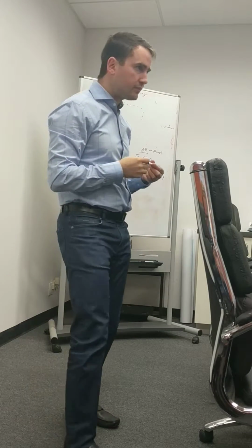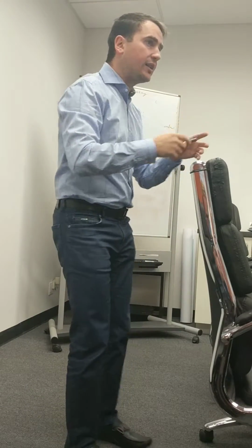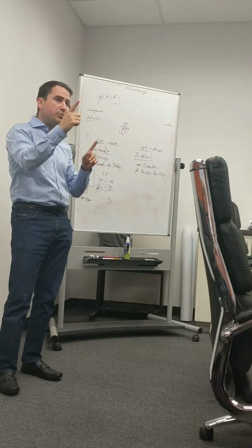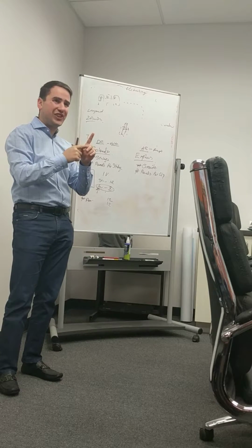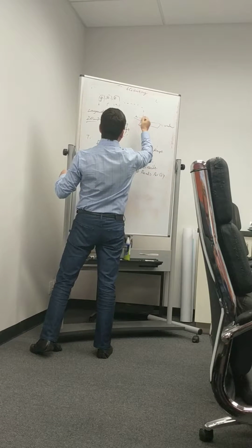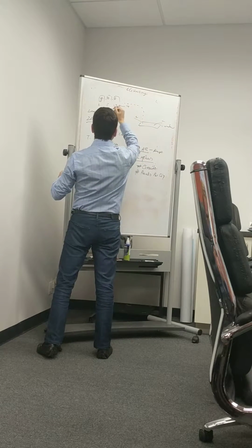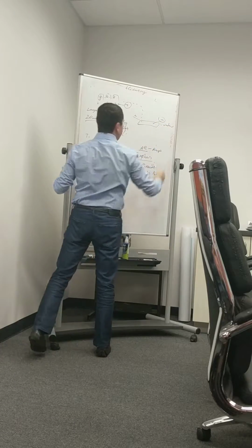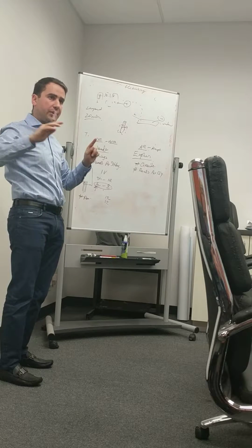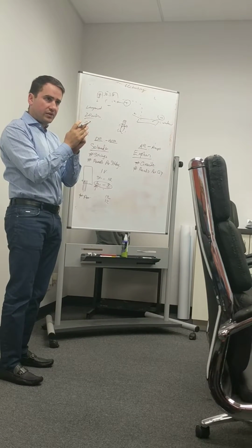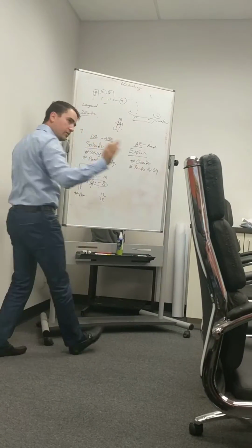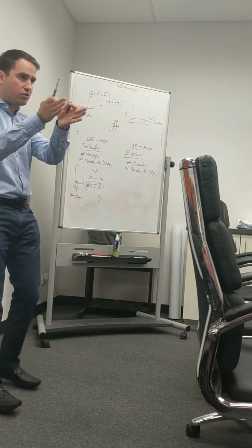They ran 2 of the positive string 2s. So exactly, most of the time, if the foreman doesn't know the proper way to do it, what they do, they put positive to positive when they have to do daisy chain. Because when you have 3 panels here and then you have 3 panels here, the positive and negative and positive and negative, this positive needs to connect to this negative. So you can have a series connection rather than a parallel connection. That's also something you need to check.